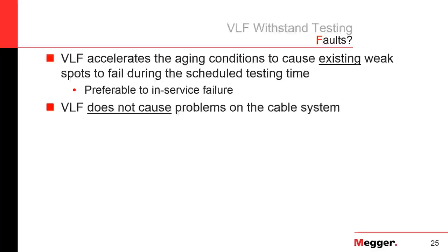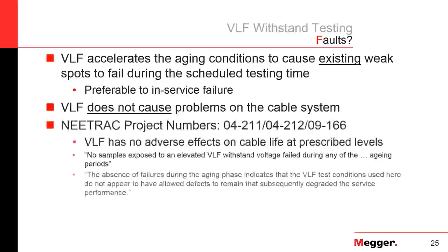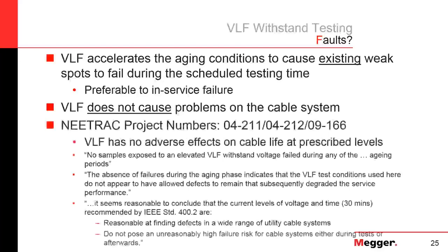So it's important to know then that VLF does not cause problems on the cable system. It only finds problems that are already existing. And NEETRAC published these papers. There's the numbers on the screen here. And NEETRAC says VLF has no adverse effects on cable life at prescribed levels.